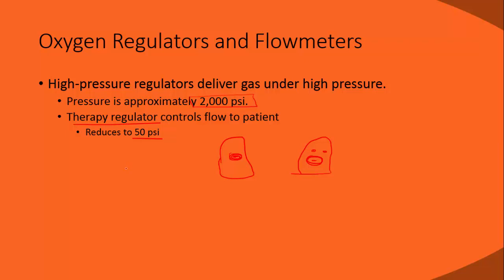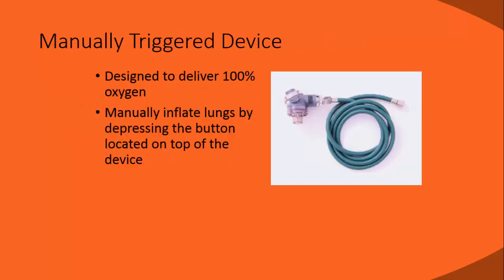So where the regulator attaches, further down in line before you get to the nipple that you connect to your oxygen tubing, there's a piece that sticks off that's threaded, and that screw side is going to provide 50 psi. That's where you would hook up your CPAP, ventilator, or inline devices. So let's talk about some of those devices.